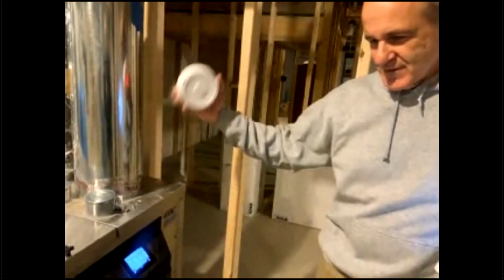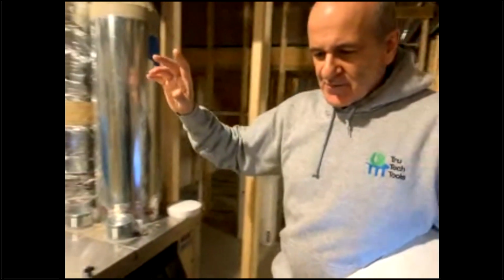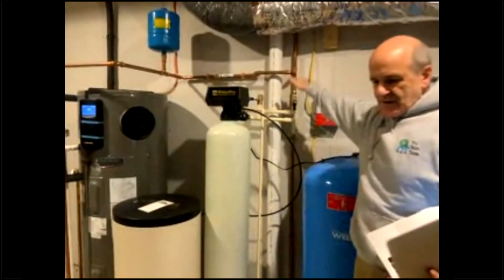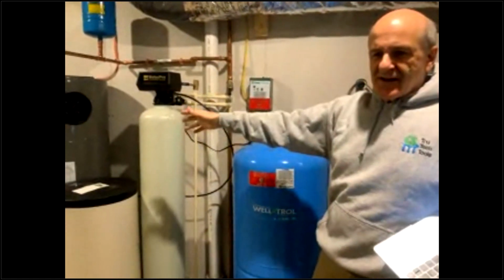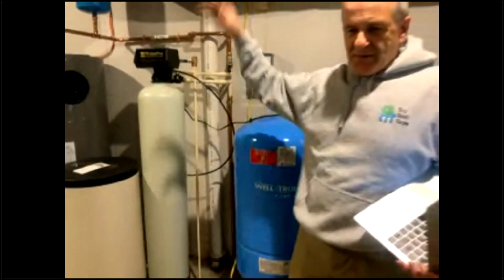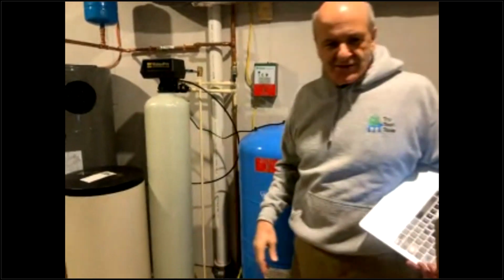Also a radon monitor, which we need. That looks like we do need. We did have installed a passive radon system, like radon resistant construction. That's this tube here that goes straight up and out the back, a 3-inch. It's sub slab open to a gravel pit area. Unfortunately, there are higher than good radon levels present. So we're going to have to go up inside a little attic area that we have, a knee wall area, and add a fan to do some powered radon exhaust.